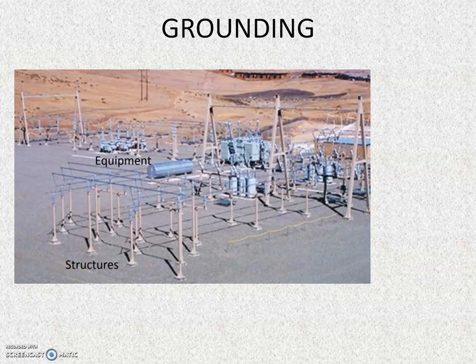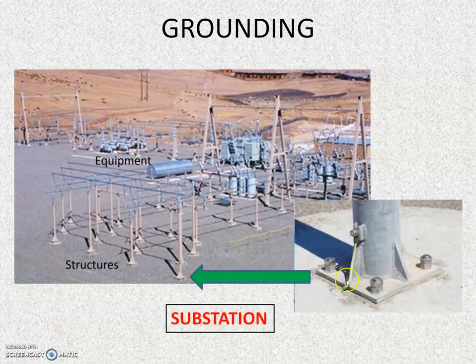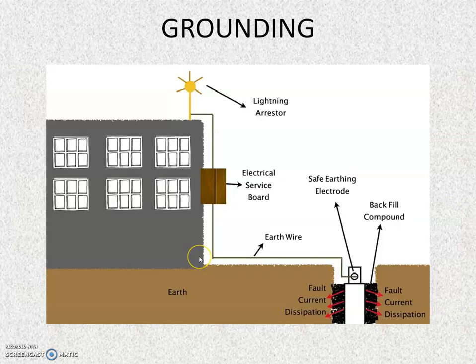This is the case of a substation where the equipments and structures are shown. These structures and equipments, everything will be grounded, and the structure is grounded like this. Everywhere these grounding connections will be provided and there will be a grounding grid. And this is the case of a building. In this case, the building has a lightning arrestor and this is the service board. These two things will be grounded. In the normal case, they will not be conducting. So in the event of a lightning surge, the current will pass through this low resistance earth path to the ground.